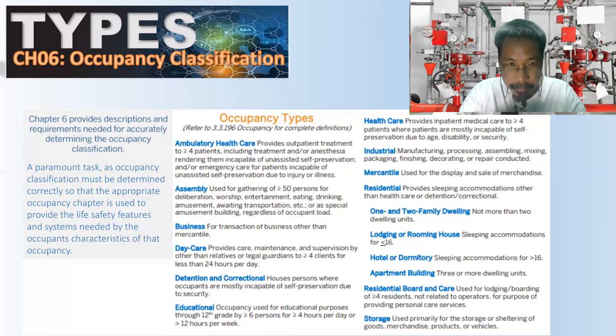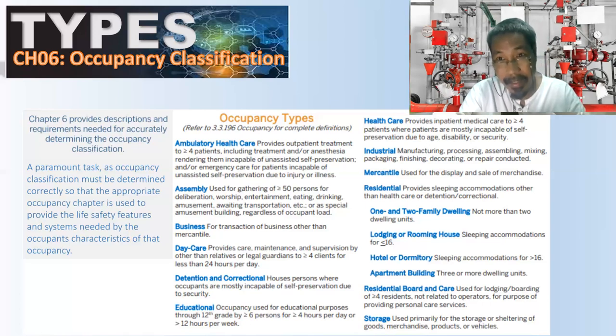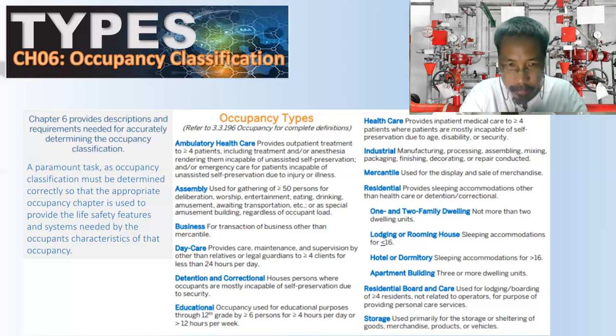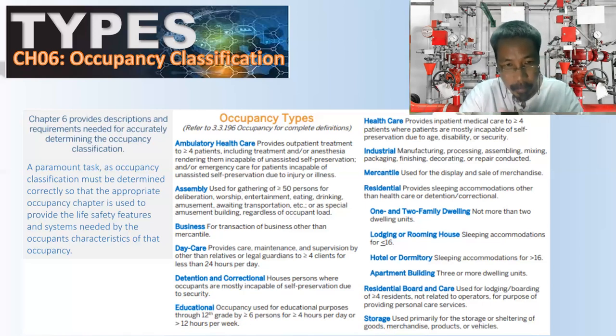Daycare occupancy provides care, maintenance, and supervision — by persons other than relatives or legal guardians — to four or more persons for less than 24 hours per day. Daycare is less than 24 hours per day; if it were 24 hours, that would be a different occupancy type such as residential.